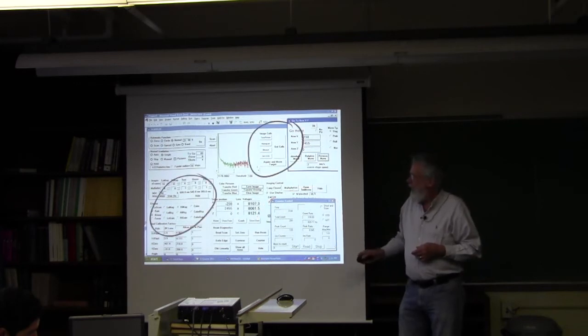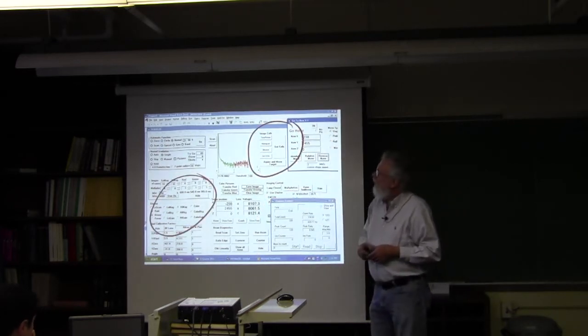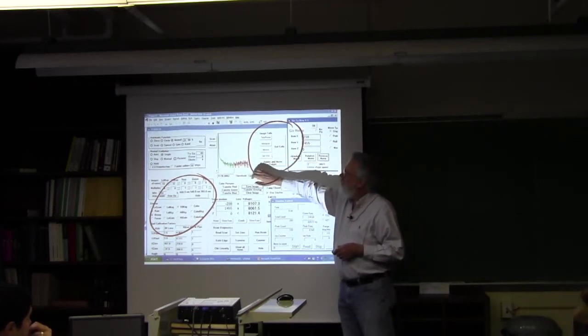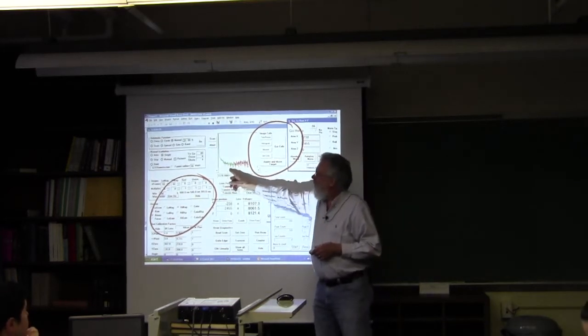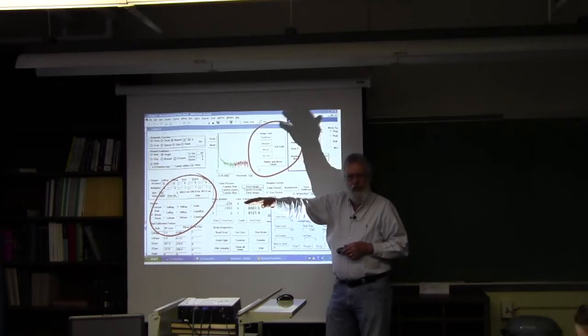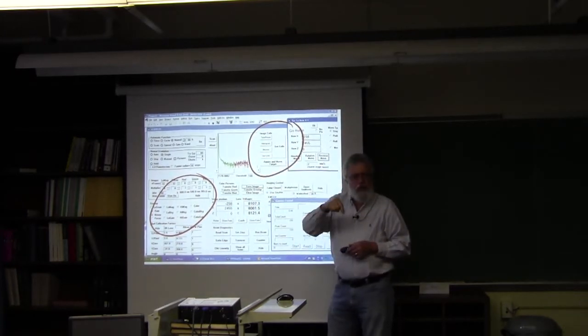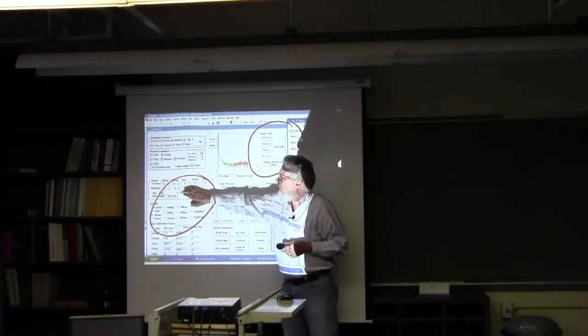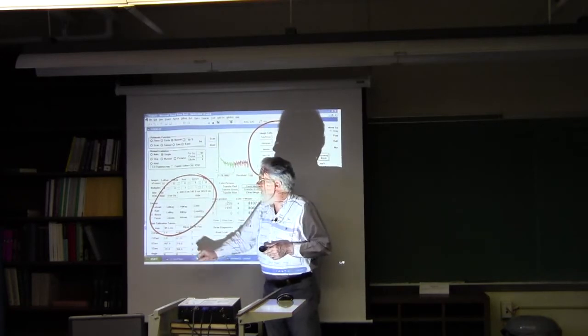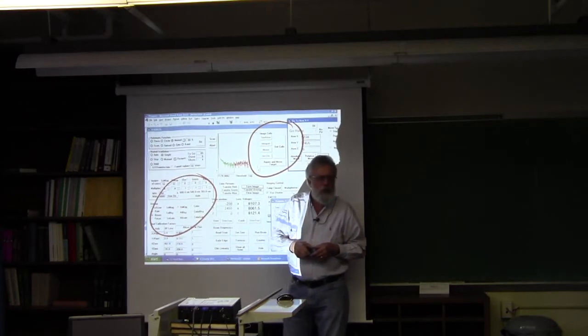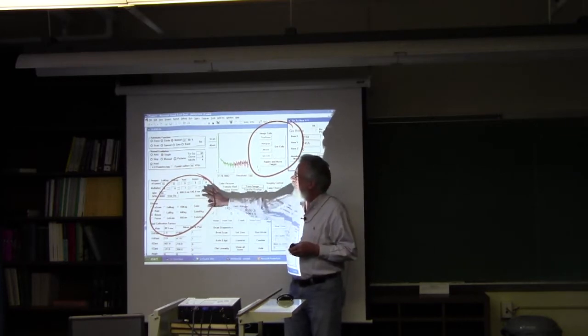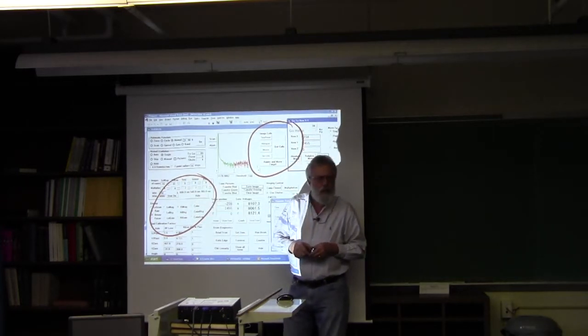These pieces have to do with taking pictures. If you click here you'll get a new picture. If you click histogram you'll generate this picture. This is the brightness and this is the log of the number of pixels that have that brightness. Binarize separates the bright areas from the dark areas, and get center of gravity finds the middle of objects that it's found in the binarization. This is for setting up the camera gain. This is for selecting which type of image you're taking: through the high magnification lens, through the low magnification lens, color. We have the capability of taking a three color image. If you have three different fluorophores you can get an actual color picture of that. The gain on the camera for the different colors is also independently adjustable.